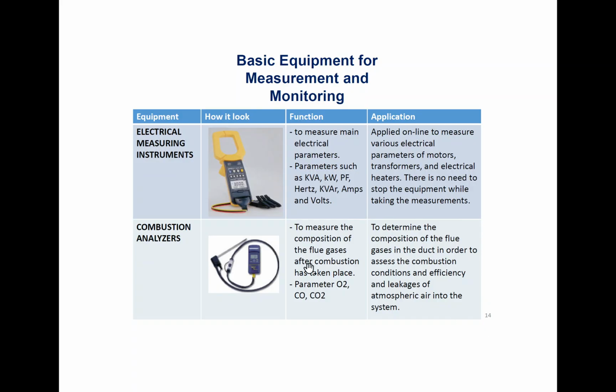Next is the combustion analyzer, to measure the composition of flue gas - O2, CO, CO2. When we analyze the combustion, we know whether our combustion is efficient or if there are leakages causing danger. If CO is released in the building it can cause poisoning, CO2 causes temperature to rise. So you need to determine that composition using the combustion analyzer.